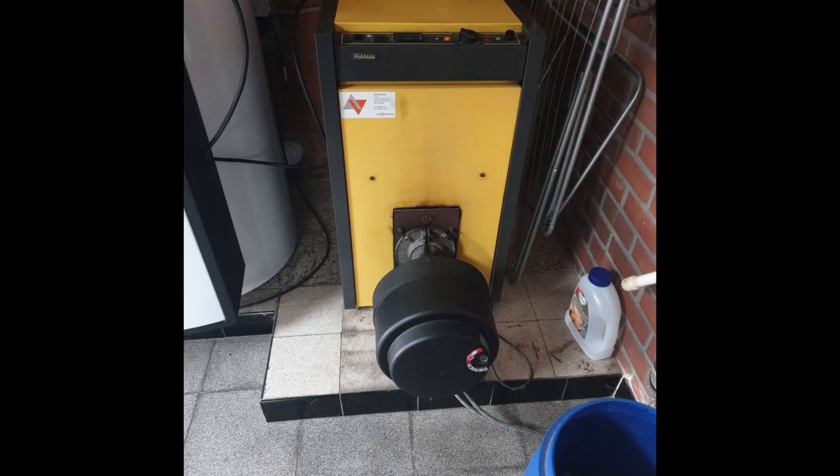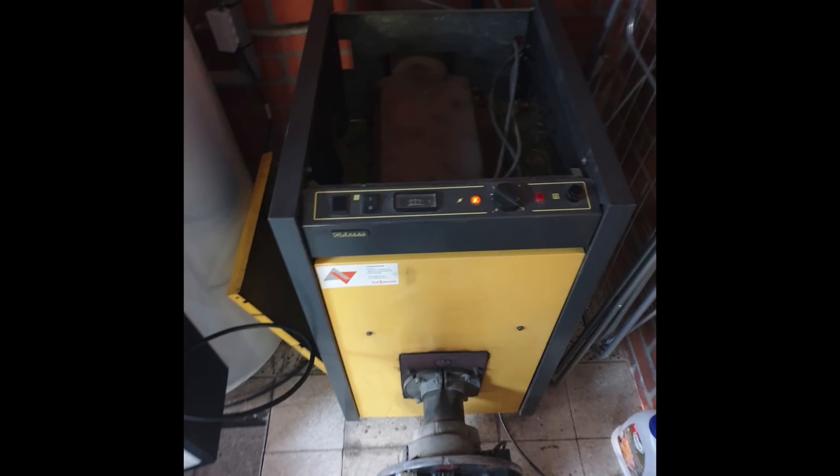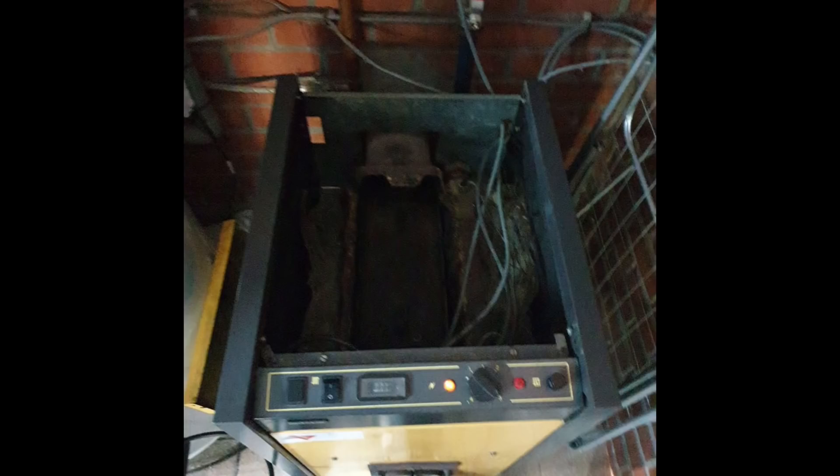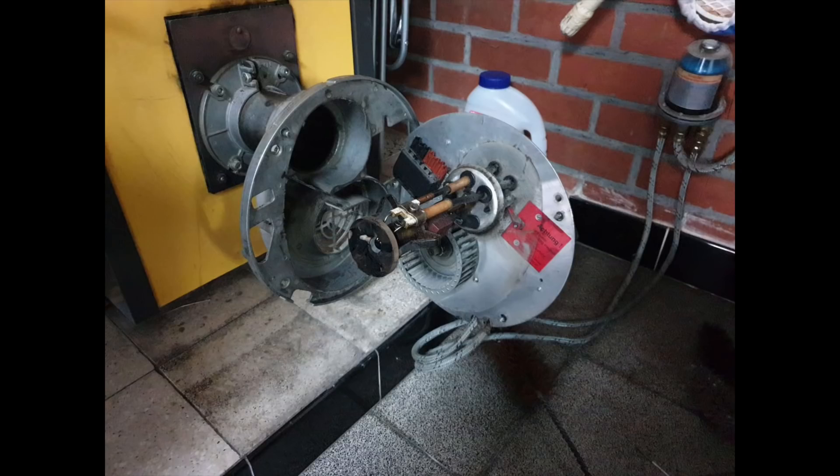Something a little different for the channel — this is a 1994 Ideal Standard oil burner, and this is a boiler service on an oil boiler. I've never worked on oil, so I can't tell you much, but you can clearly see it's getting a good clean-out. He's taken the baffles out, got his brushes in, baffles laid out on the floor, and he's checking the burner.